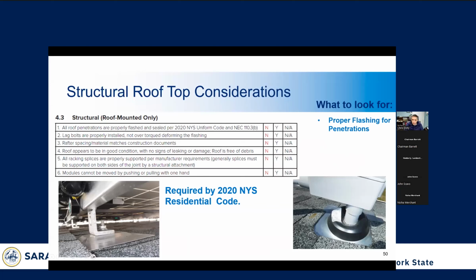All right, so now we're going to go into the rooftop. The guidebook has a section for rooftop PV attachments and penetrations. So in addition to verifying that they're present, you have to verify that they're installed properly. The guidebook gives examples of proper installation. You may see flashing that's not installed correctly according to the manufacturer's instructions, or things like that. It's important for contractors to follow these guidelines and for inspectors to know what to look for.